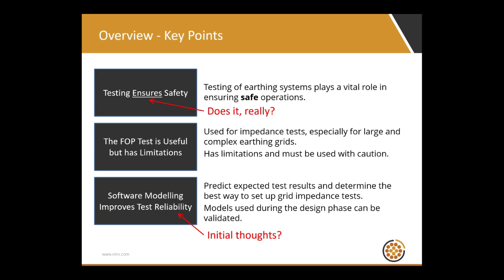The fall of potential test is very widely used, particularly for large and complex earthing systems. But we must remember, and I think in industry we don't really understand its limitations. This presentation will demonstrate those important limitations that you must consider when you're using the fall of potential test for your earth grid impedance measurements.